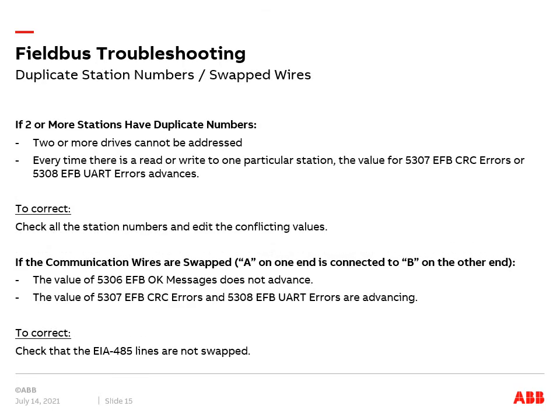Let's talk about duplicate station numbers or swapped wires on a network. If two or more stations have duplicate numbers, two or more drives cannot be addressed. Every time there's a read or write to one particular station, the value for 5307 EFB CRC errors or 5308 EFB UART errors advances.